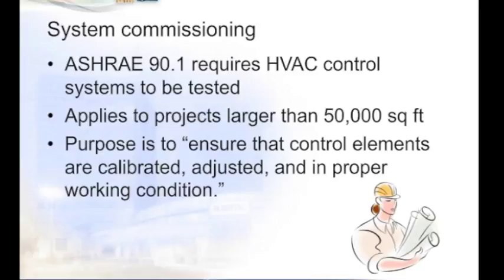The commissioning requirement in 90.1 applies to projects over 50,000 square feet. It's interesting how 50,000 square feet is used in ASHRAE. LEED also references 50,000 square feet for enhanced commissioning requirements, and the similarities there are hard to ignore. And then the final item that 90.1 discusses on commissioning, the quoted purpose of this commissioning requirement, is to ensure that control elements are calibrated, adjusted, and in proper working condition.